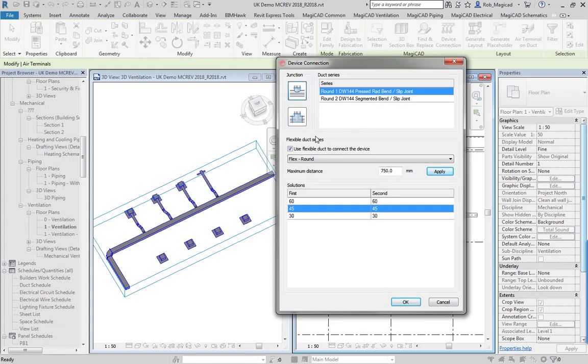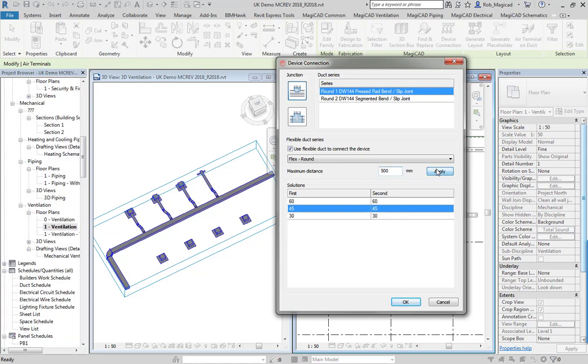And you can choose, using normal MagiCAD functions, whether it's a T or a tap at this point, which duct series to use, and from previous releases you can also put the rectangular to round flexible connection at the end of the duct onto the air device. You can choose the length for that as well — if I press 500 and press apply, it will update that to suit.